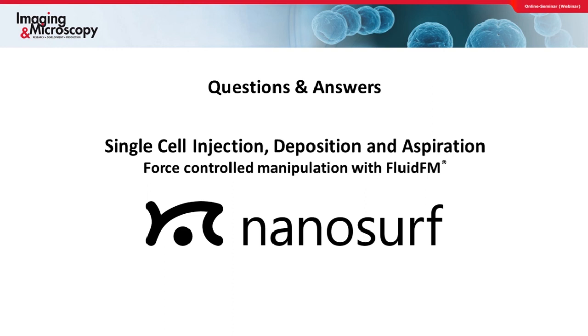There are some coworkers who have used small washes in bleach or this kind of solution. I think it's not that good because it doesn't prevent the interaction between the cell and your probe, such as the adsorption of proteins on the surface of your probe. So you may damage the cell if you don't have the coating. Short exposure to bleach will also not damage the probe, but longer exposure to some solvent or bleach would unglue the chip from its holder. So we usually avoid cleaning the probe.